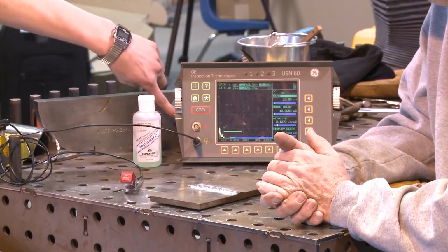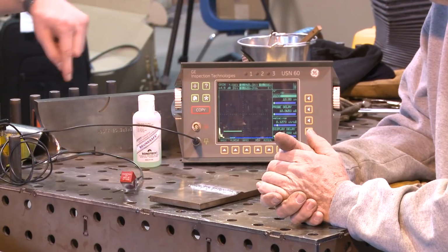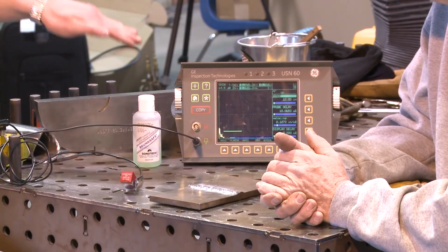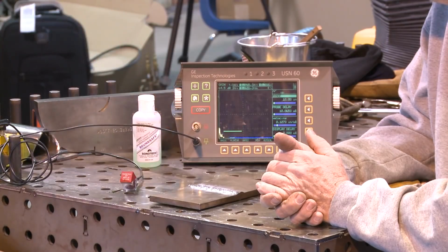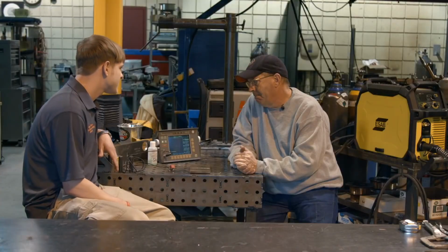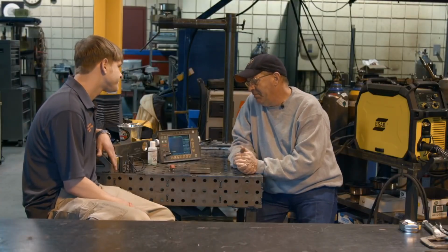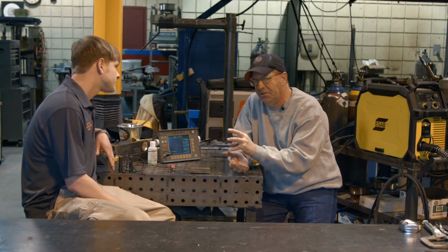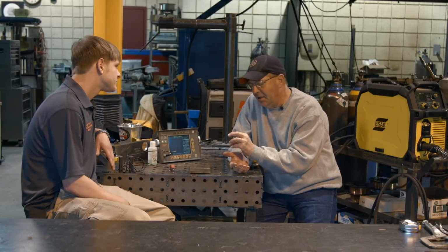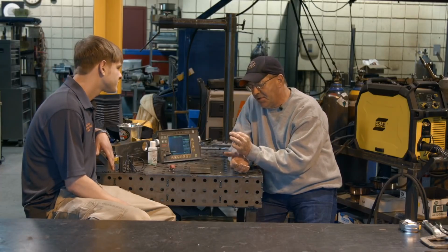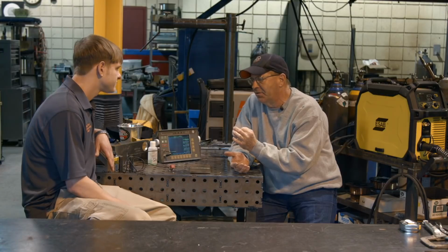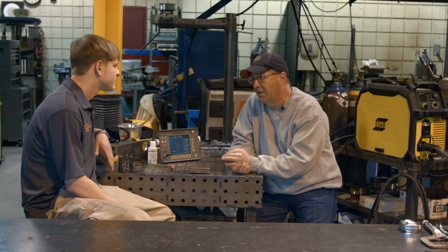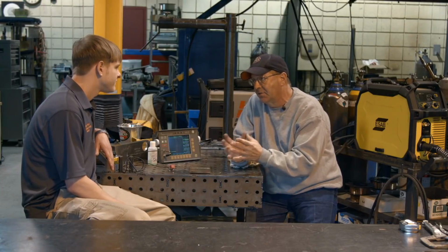And we also have a 60 thousandths hole that I set my sensitivity to, meaning how high my signals jump up here on this screen is all comparative to this 60 thousandths hole that I calibrated on. So then I can give you size estimates. Oh, okay. Pretty accurately. So, I've been out in the field and out in the refinery, and I've been asked to do certain things on a certain place, and I'll get a UT shot of a wall thickness of a piece of pipe that's been in the refinery for a long time. I want to know how thick it is before I put a weld on it, and we're going to bore through and do a valve or something.